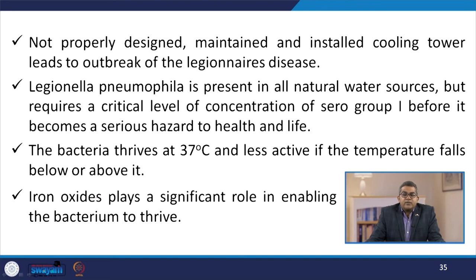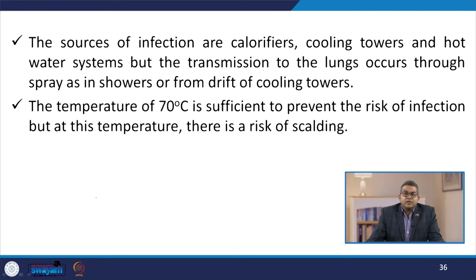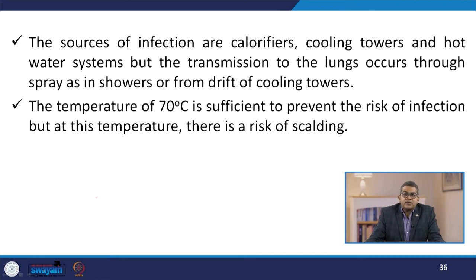The bacteria thrive at 37 degrees Celsius and are less active if temperature falls below or above it. Iron oxides play a significant role in enabling the bacterium to thrive. The sources of infection are calorifiers, cooling towers, and hot water systems, but transmission to the lungs occurs through spray — as in a shower — or in the form of drift from a cooling tower. A temperature of 70 degrees Celsius is sufficient to prevent the risk of infection, but at this temperature there is a risk of scalding.